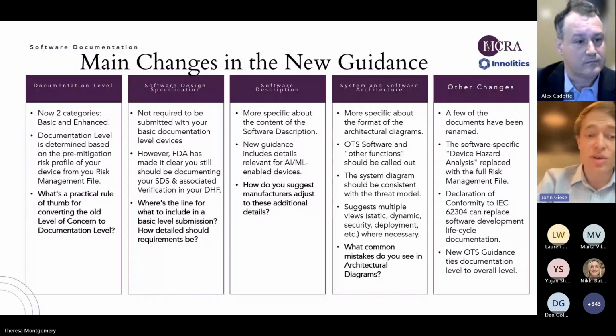and finding the right balance is kind of an art. So with respect to requirements, what we generally suggest is focus on requirements that trace back to risk management. Those tend to be very important requirements. Also focus on requirements that trace very directly back to the intended use. And cybersecurity is another big area, of course, as well.